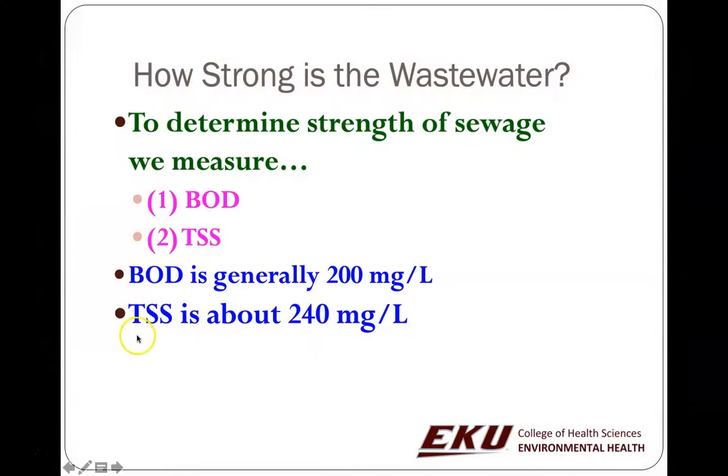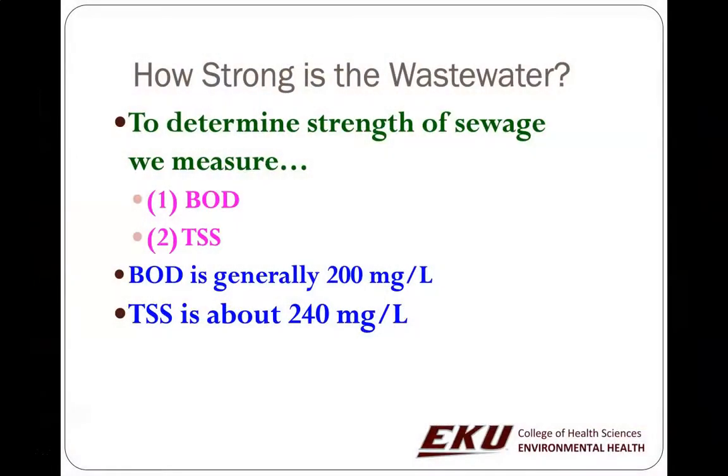Total suspended solids equate to about 240 milligrams per liter, so it's a pretty good amount in our wastewater. You can put the sewage into a big cone and let it settle. They're settleable solids, and you can measure them. Suspended solids will actually settle out, and you can measure the height on this big cone, which has labels that can convert that value for you.